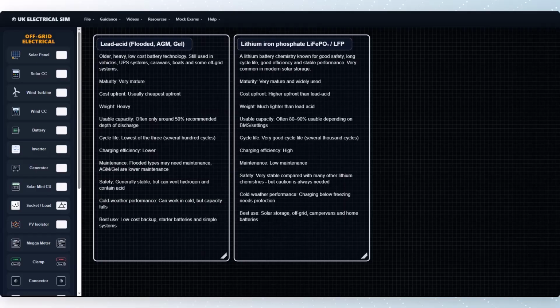The main downside is cost. LFP batteries are normally more expensive upfront than lead-acid batteries, although over their lifetime they can work out cheaper because they last longer and provide more usable energy. LFP batteries also need a BMS, which stands for Battery Management System. The BMS protects the cells from overcharge, over-discharge, excessive current, and unsuitable temperatures.